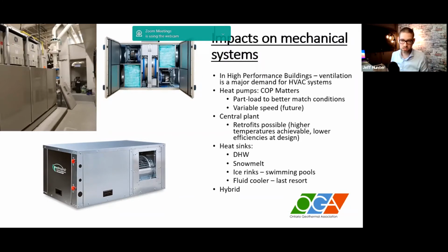Now in retrofit situations, and I've gone through this myself with retrofits of schools, existing schools may be on conventional systems, boiler, cooling tower with existing heat pumps. Sometimes it's tough to take a heat pump from the 70s or from the 80s that was on R22 refrigerant and upgrade it to a new heat pump that's on a newer refrigerant. They may not be the same efficiency comparatively, and they might be larger units, so you're bound by those constraints, but COP does matter. Now, in larger buildings with central plants, there's an image here on the top left. That's a modular heat recovery chiller.